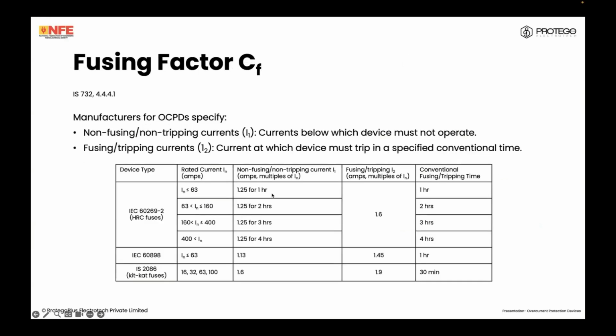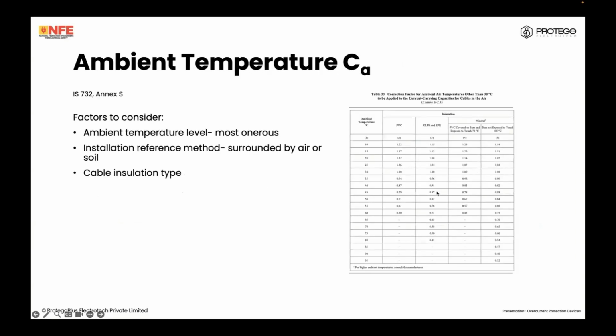Okay. Going back to our conventional tripping times, we will see that HRC fuses have a fusing current of 1.6 IN, which means that for say a 10 amp HRC fuse, 60269 fuse, in an overload condition, it will trip at 16 amps in 1 hour.